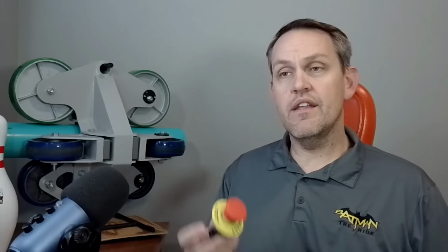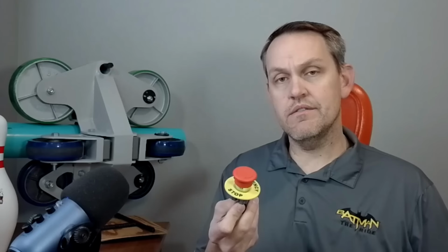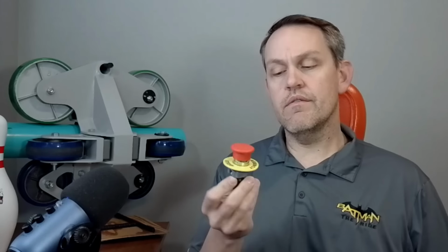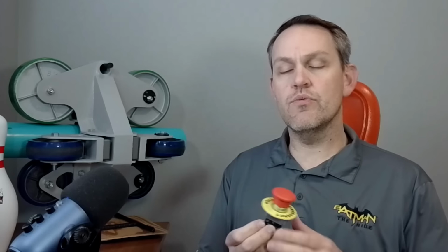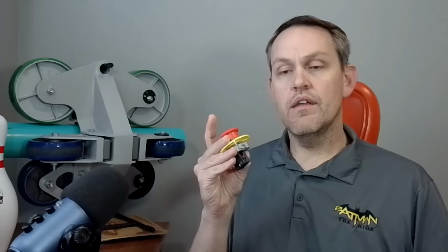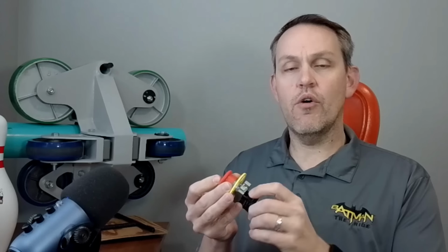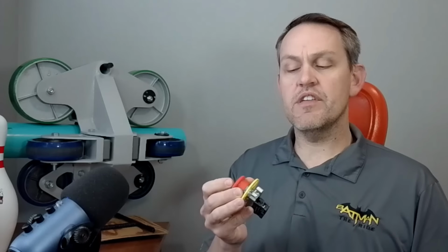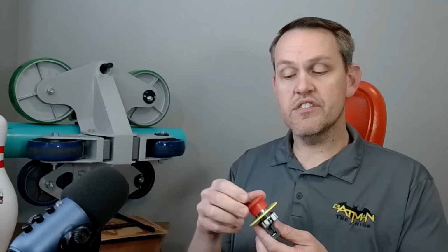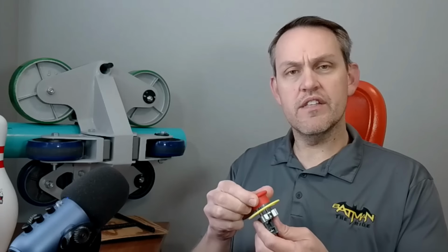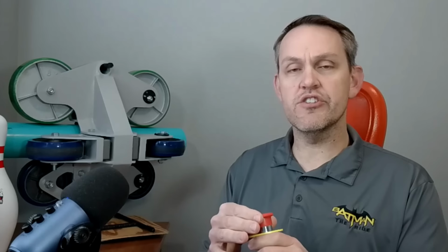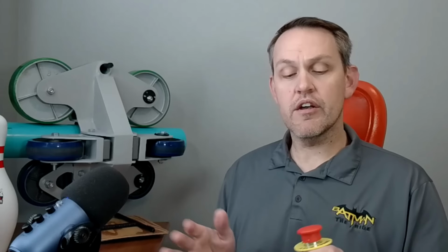Next is the e-stop. This guy is located on pretty much every single ride, and they typically need to be tested. So most every ride, the e-stop is put in such a fashion to where when you press the e-stop, it opens power to something. So power was going through here, and it opened it up. Now typically e-stops aren't something they just want you to pull back up all of a sudden. It's a mushroom head. What are mushroom heads good for? Slapping. So that is one thing that OSHA and everybody else wants to make sure that anybody can just go and slap the thing down and the ride comes to a stop.